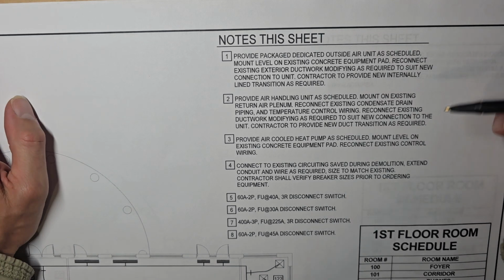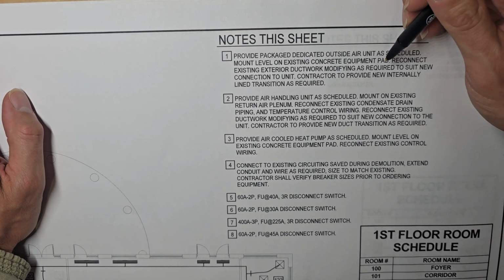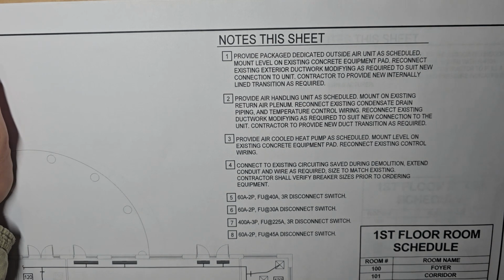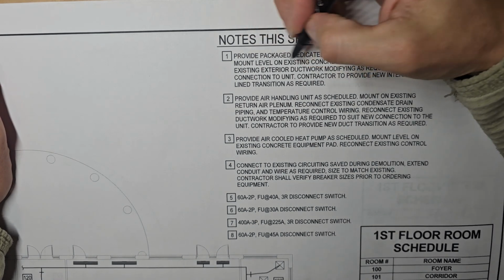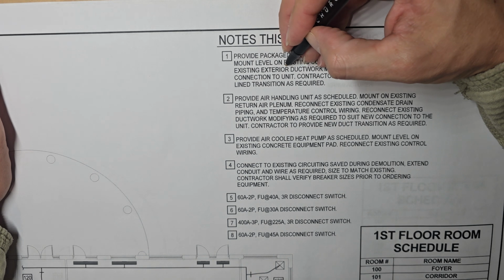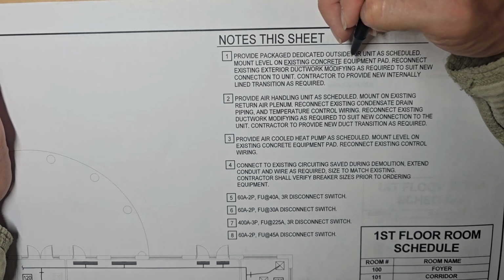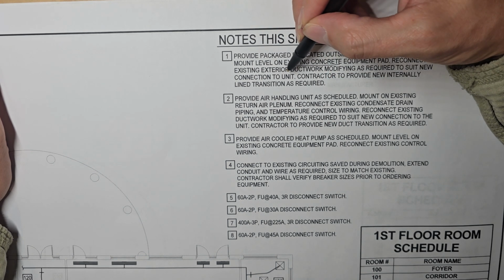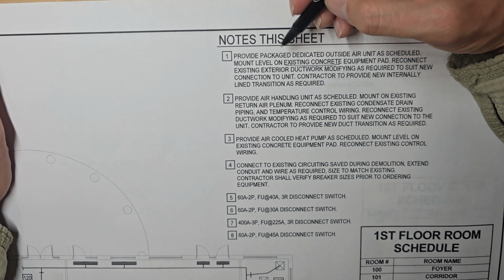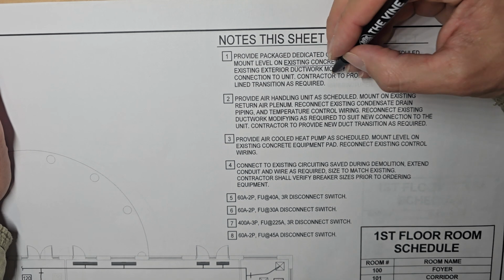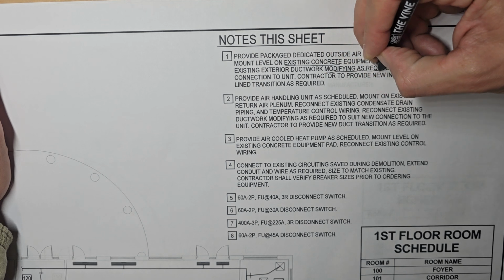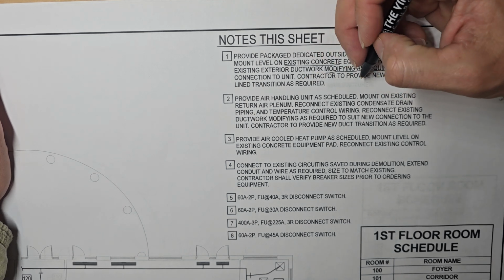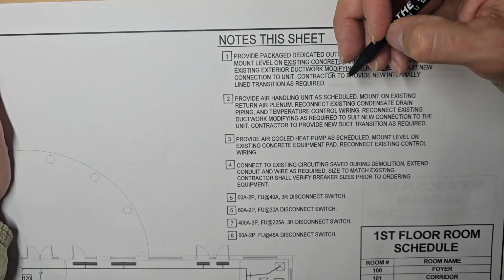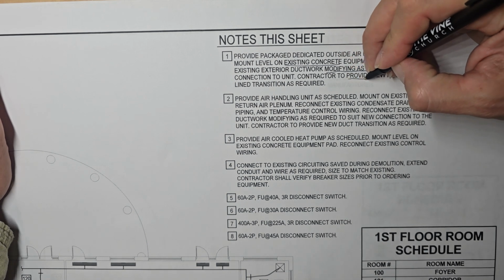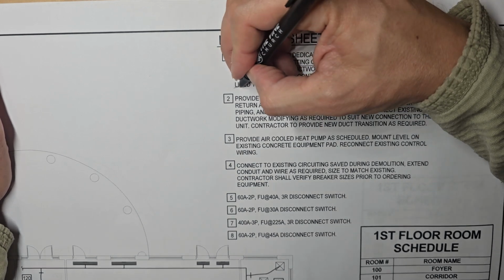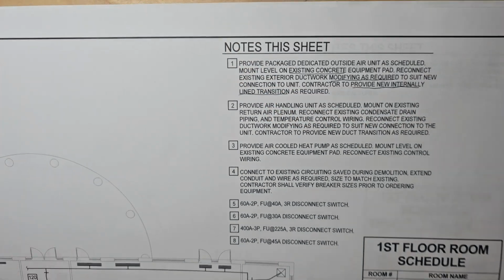Provide package dedicated outside air unit as scheduled. So we've got the schedule on the next couple pages. We're going to mount it on existing concrete. That's nice. Reconnect the existing exterior ductwork, modifying as required to suit new connection to unit. All right, might want to make sure we add that. Contractor to provide new internally lined transition. All right, so number one.